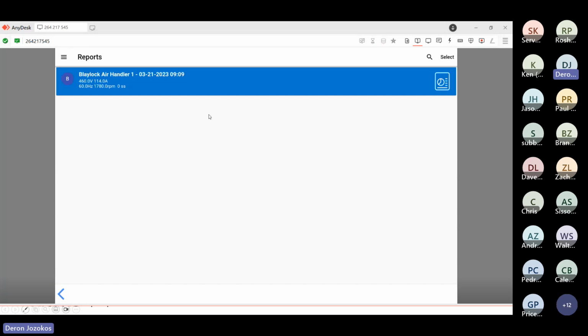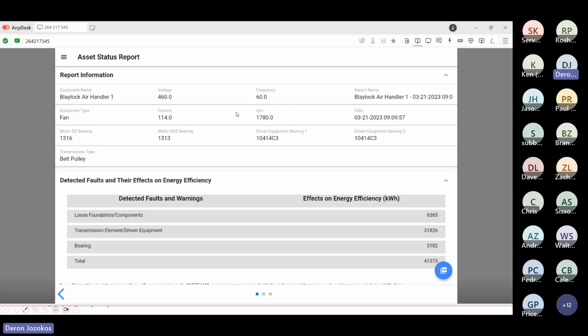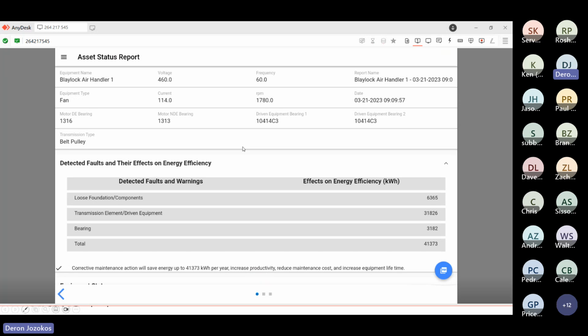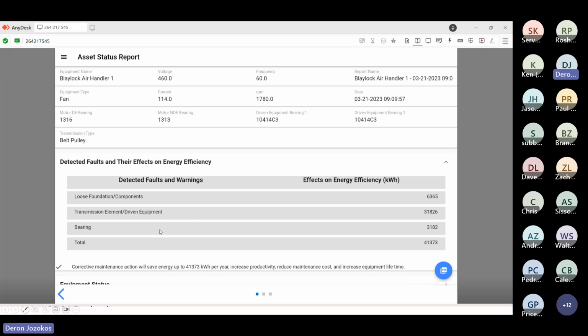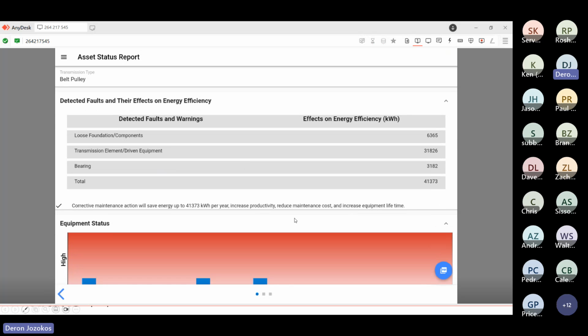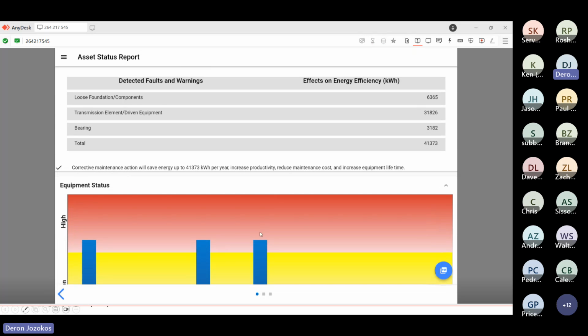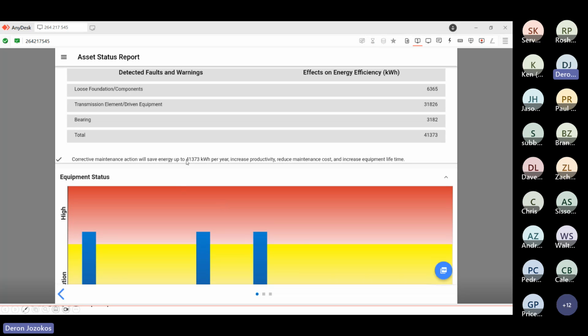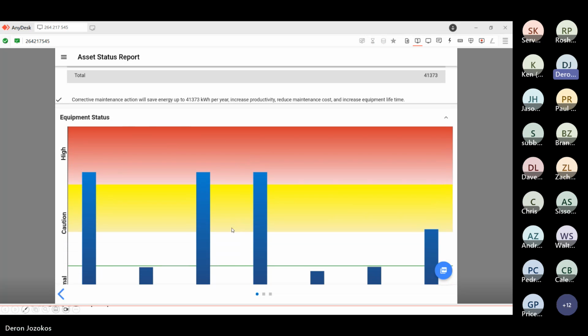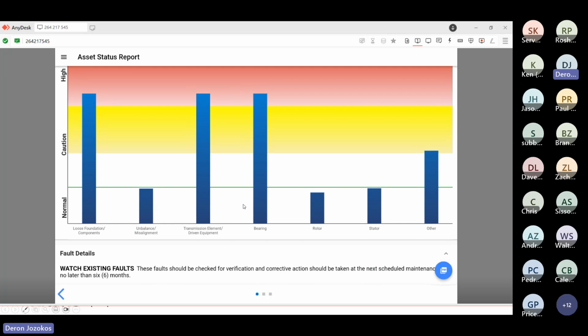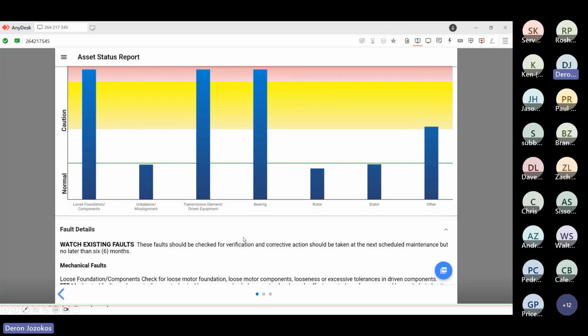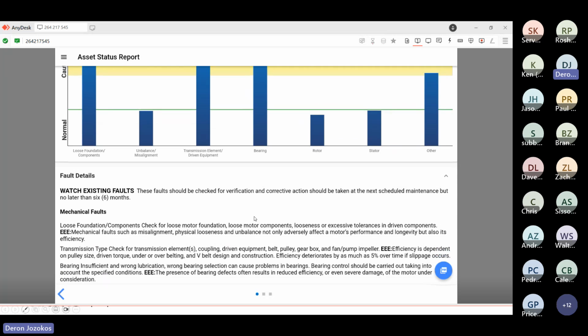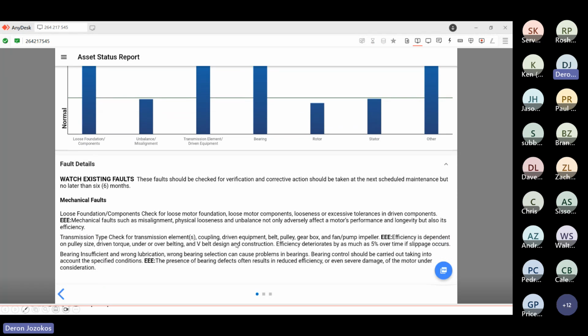Okay, so we ran our 7-minute test. At the end of the test, you'll get this pop-up. This is what it'll look like. Your actual report right here, and this is a good example. Triple E number, the effect on energy efficiency. So it found loose foundation components, transmission elements, bearing, totaling 41,373 kilowatt hours. Corrective maintenance action will save that amount in energy consumption. So you can see here we have 3 in the red, and we don't just tell you you have a problem. We also give you some things to go and check and look for.